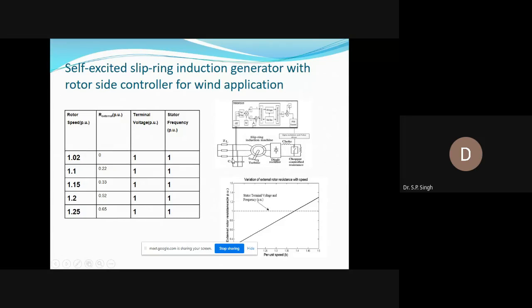This is for a wound rotor self-excited induction generator in standalone mode, and the basic concept remains more or less the same, in a different way. When we are operating the machine at rated speed, with suitable capacitors we can get the rated voltage. Under that condition, at synchronous speed, there is no voltage induced in the rotor winding.